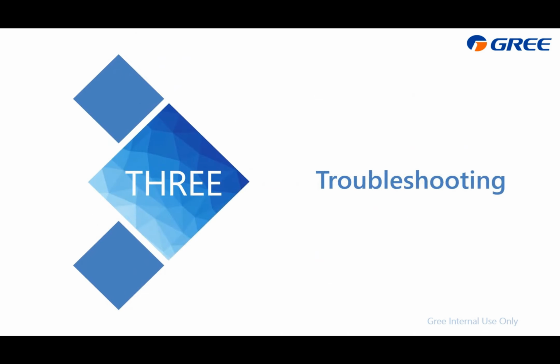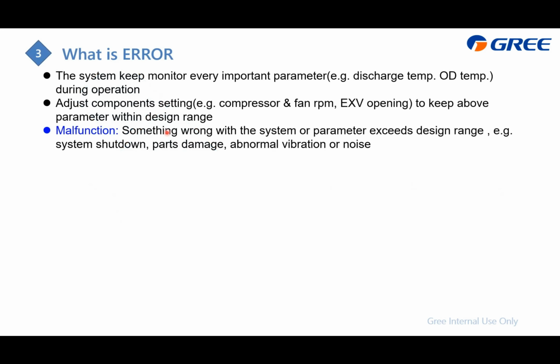For the next part is the detailed troubleshooting. First of all, what is an error? In the chiller system, we always monitor every important parameter like the compressor discharge temperature and pressure, and also the outdoor temperature. For these, we adjust the component settings like the compressor or the outdoor fan RPM and even the EXV opening to keep our important parameters in the desired range.